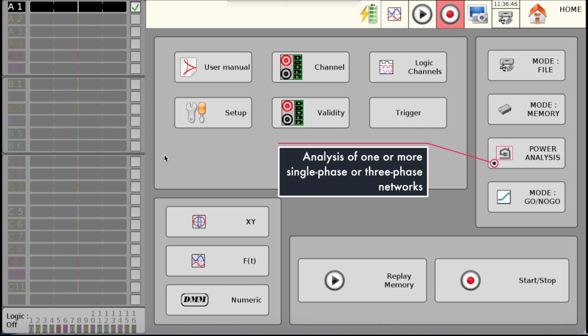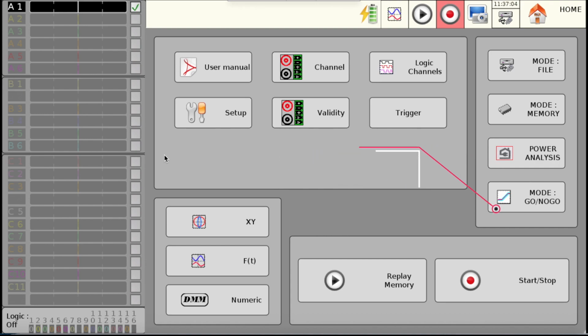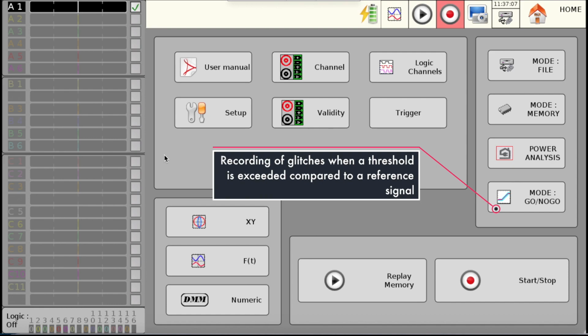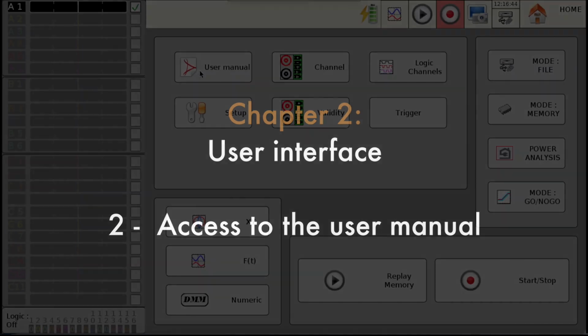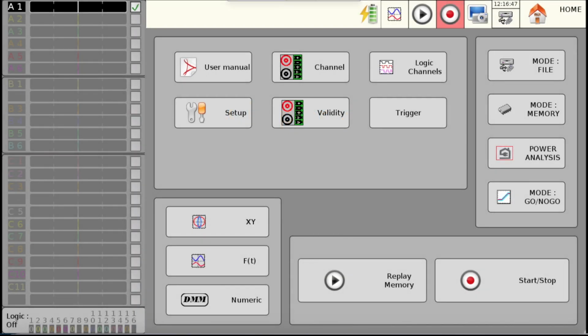Power analysis allows to analyze single-phase or three-phase networks. It can analyze up to 4 networks simultaneously. It allows to measure all types of physical values related to power analysis, such as power, harmonic, current, voltage, and others. Mode Go-No-Go allows to record when the threshold limit is exceeded. By clicking on User Manual, you have direct access to the PDF manual of the device.